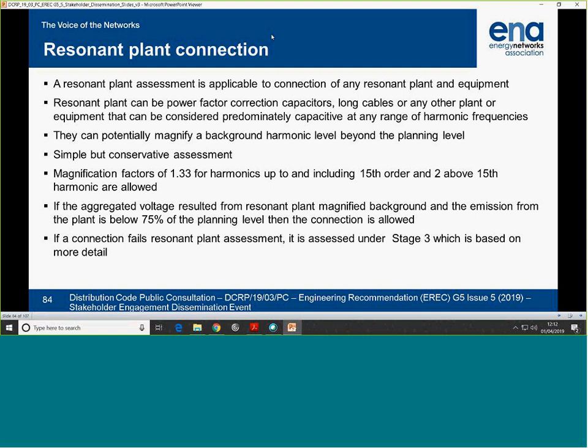Do a simple assessment. If you've got an assessment of what your cable length and type of cable is going to be, because if you know you've got 600 amps or 700 amps, you'll have a size, and you may roughly know what cable configuration, flat formation, you can probably do a resonant calculation on that cable very readily, and understand whether that length brings it into the area, i.e. the 50th. If it comes into the area, then you know you might have an issue. As soon as you do your 1 over LC calculation for that length of cable, you know, oh, hang on a minute, I've got a resonant cable here. Yeah. And if you find that it's way up in the higher range, then you can think, well, it won't be a problem. I'll wait until I get the background measurements back, and then decide.